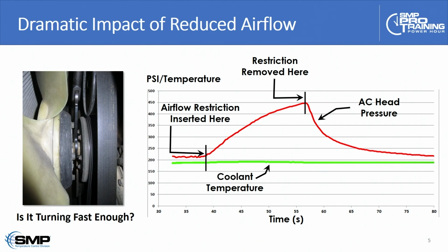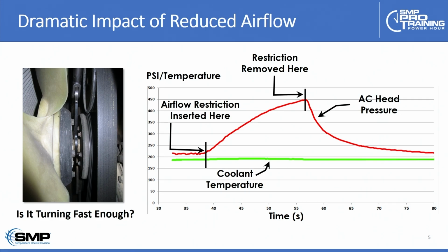The powerful visual takeaway here is that by just interrupting airflow across that condenser for a very brief period of time, you can see that air conditioning head pressure virtually doubled. The key point I want to get across is that this is obviously a pretty dramatic effect, but anything that affects airflow through the condenser will have a significant impact on air conditioning performance. That's really the point I want to communicate here.